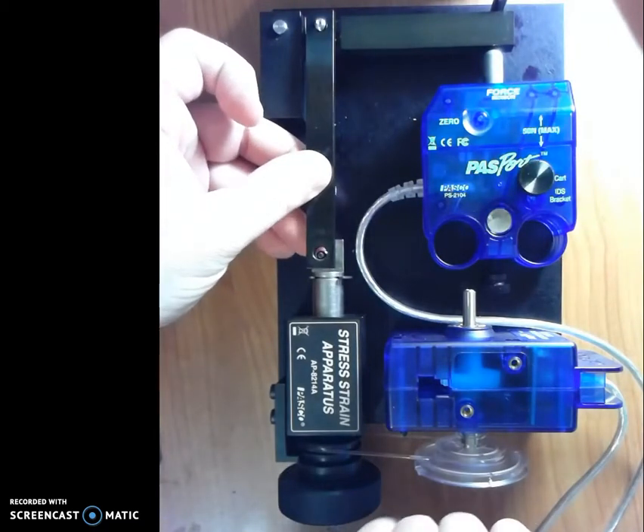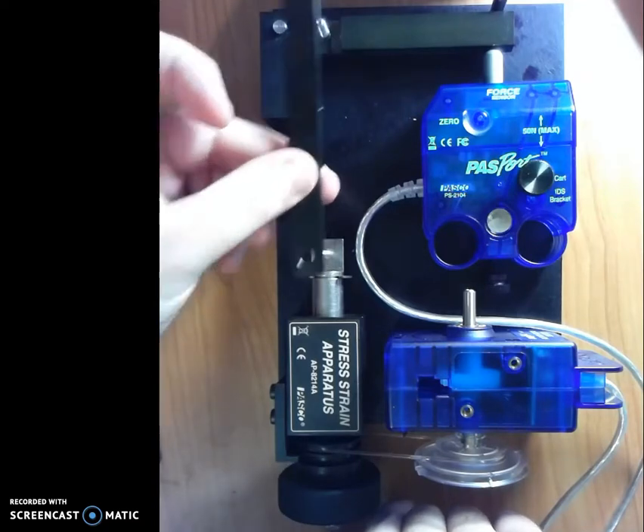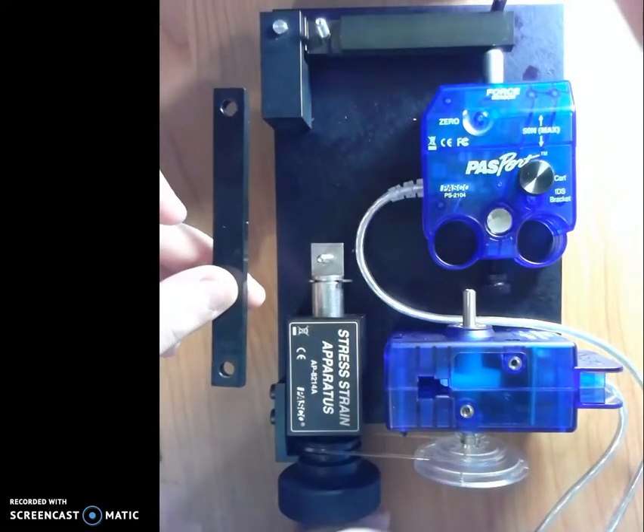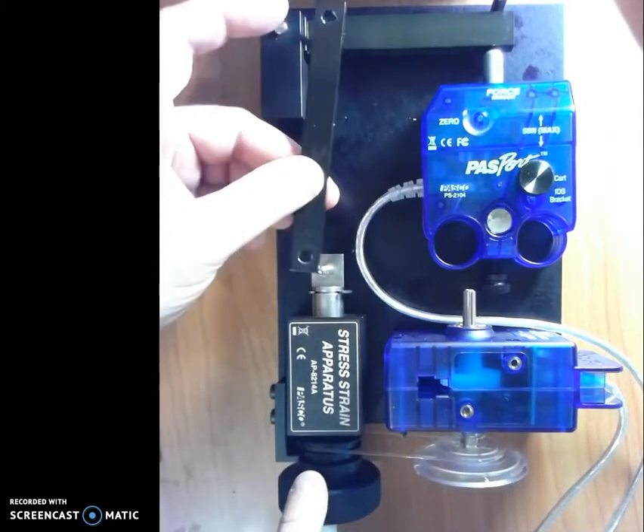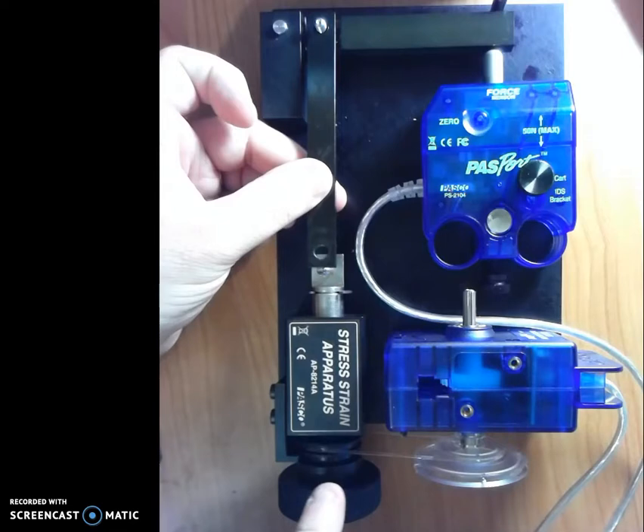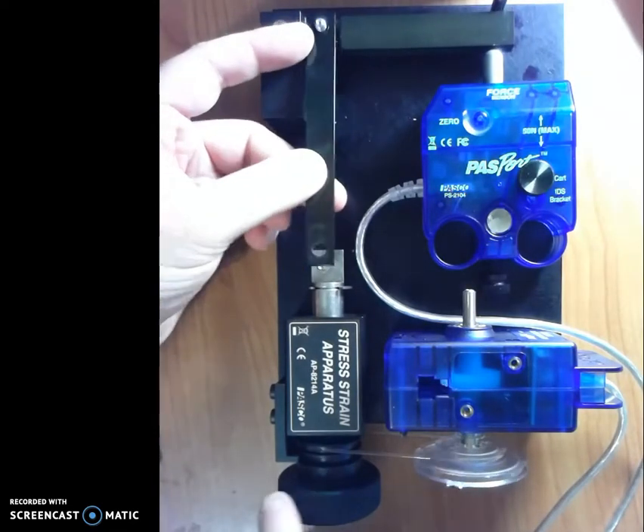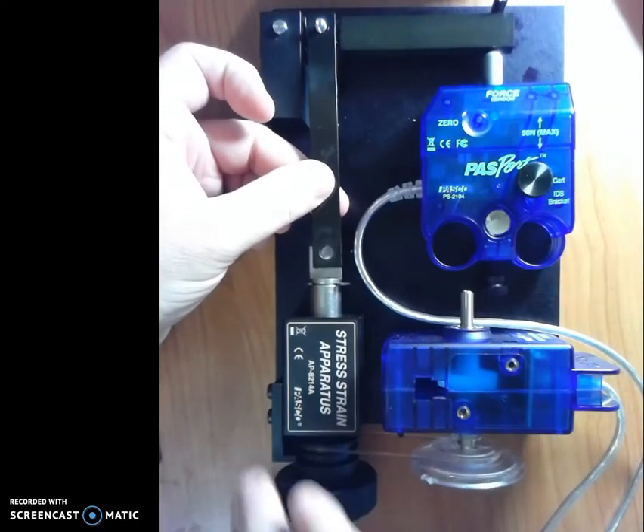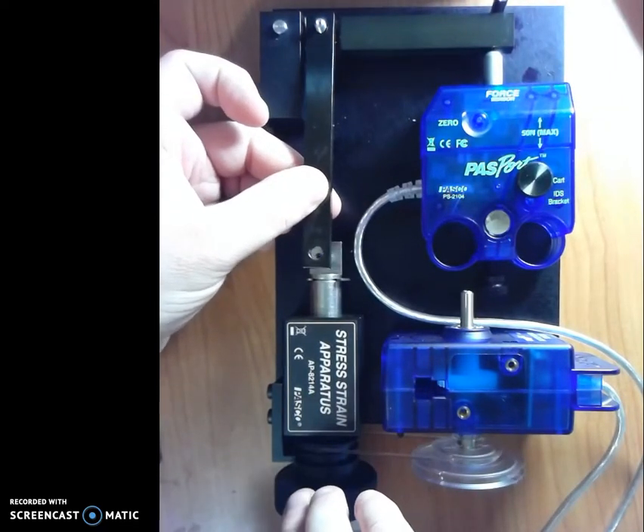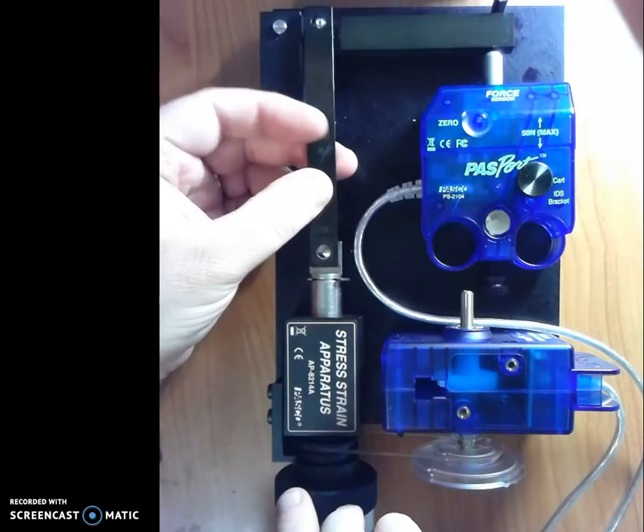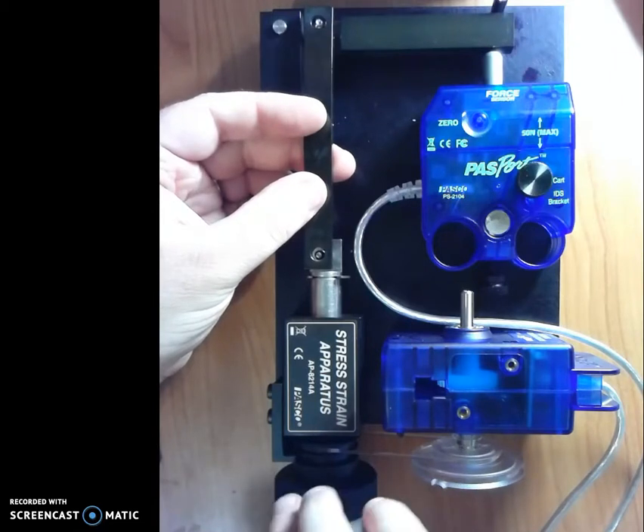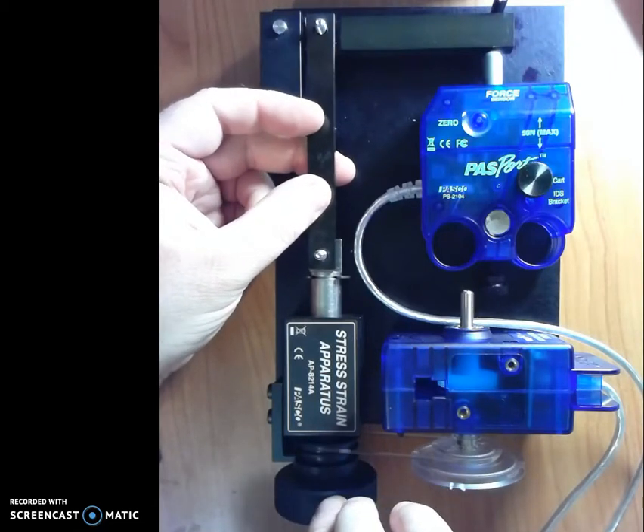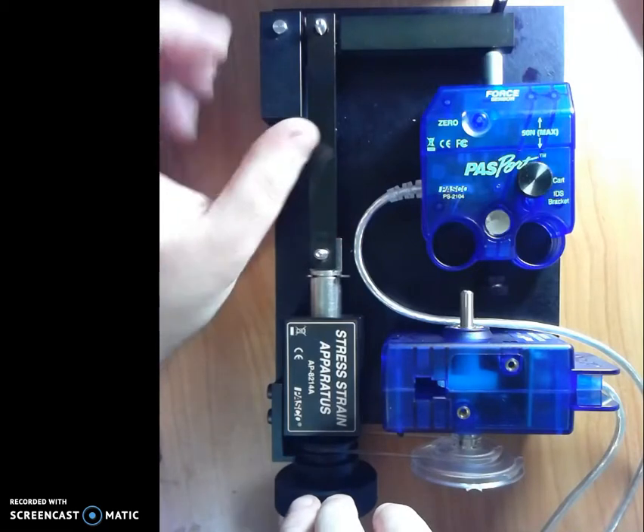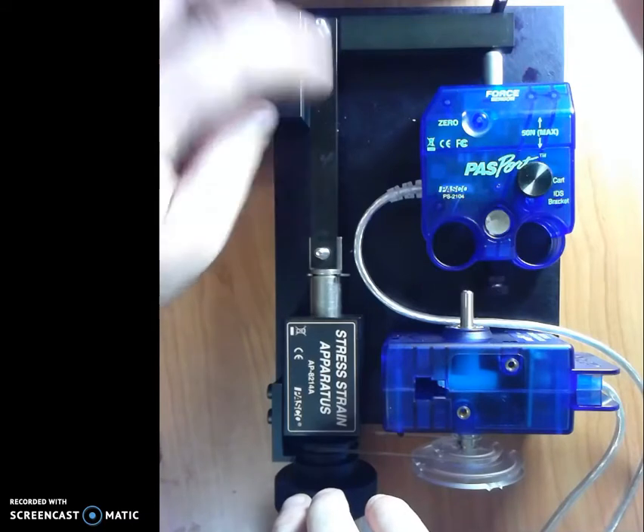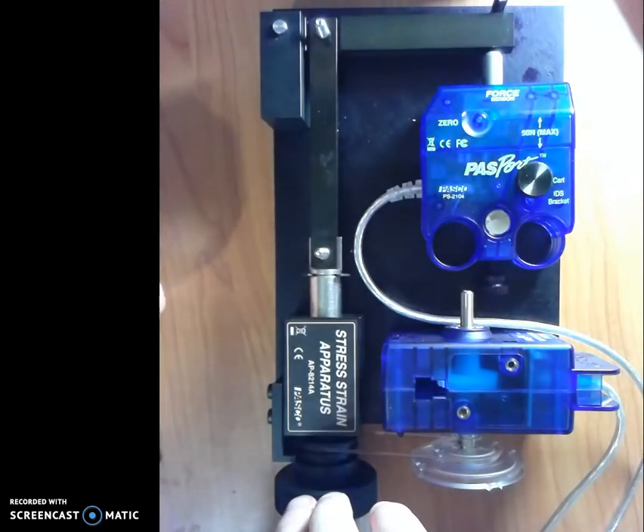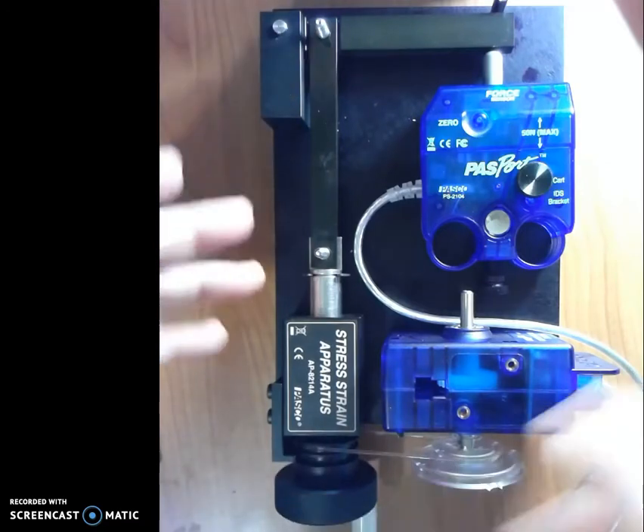If I put the calibration rod on, it should fit perfectly. You might be in a situation where, I'll turn this guy, maybe you try to put the rod on and the rod is too short, or maybe you try to put the rod on and the rod is too long. Either way, you'll have to adjust in most cases so that the rod fits on perfectly. And like I said, I cheated. I kind of did it in advance so I would have the perfect fit, but I'm going to put it on until it fits perfectly, and it should slide all the way down past the threaded part of the rod onto the unthreaded part of those two rods.